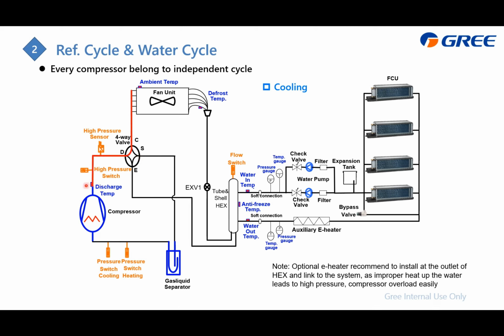Coming out from the compressor, the high temperature and high pressure gas will flow to the outdoor heat exchanger to release heat. Then the gas will become liquid and get expanded at this EXV. From here, it will be low temperature and low pressure liquid, and go to this one to absorb heat, which is doing cooling to cool down the water. So the refrigerant itself will become gas and flow back to the gas liquid separator. After separating the liquid part, the 100% gas will flow back to the compressor.